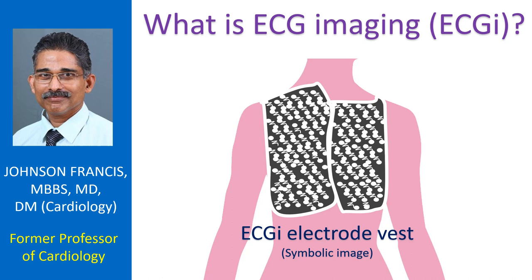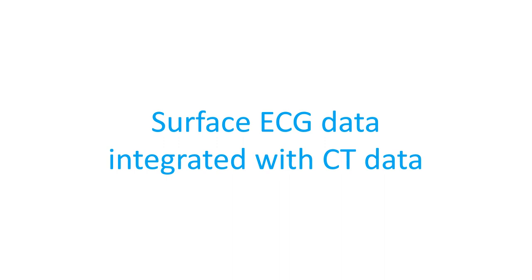The vest has three multi-electrode panels: front left, front right, and back. Connectors from the electrode vest are connected to the Cardio Insight workstation. The chest is shaved and prepared with a non-alcoholic hypoallergenic solution. The front left panel is applied first, followed by the front right and back panels. Panels are secured with medical tape, and a CT scan is done with the vest on.